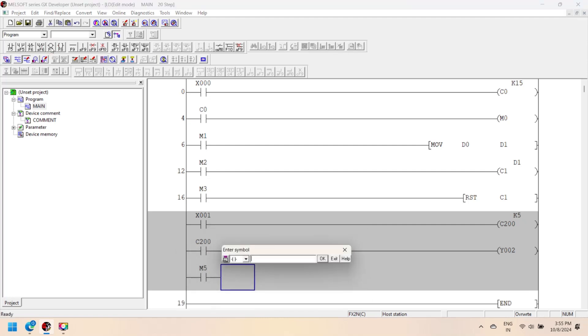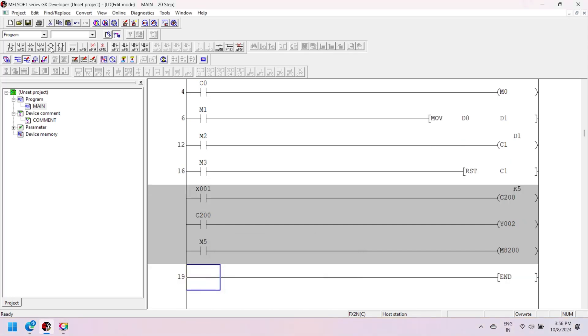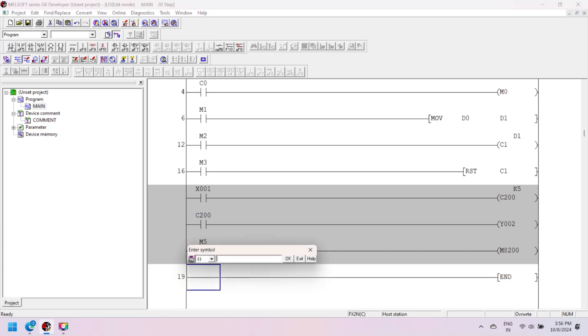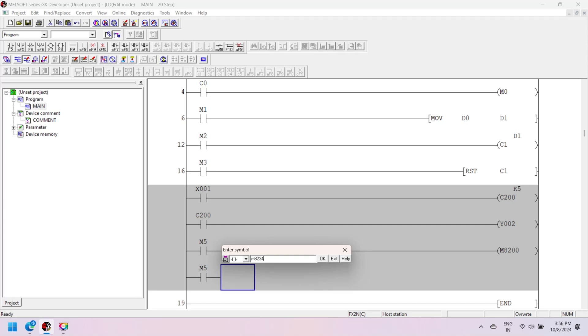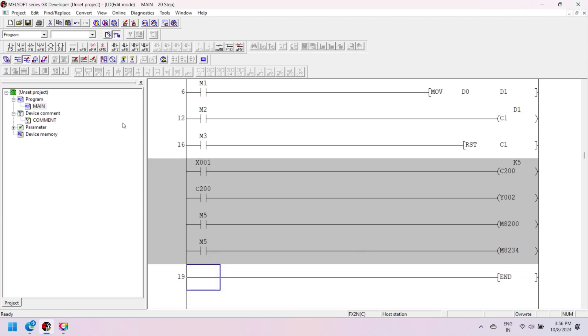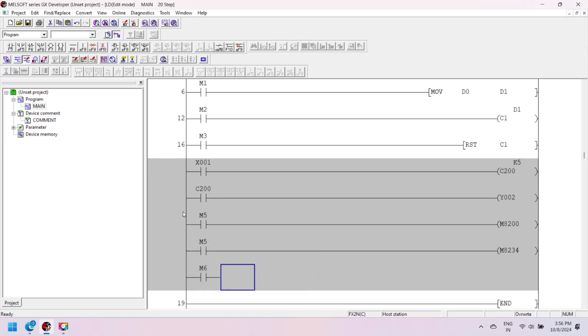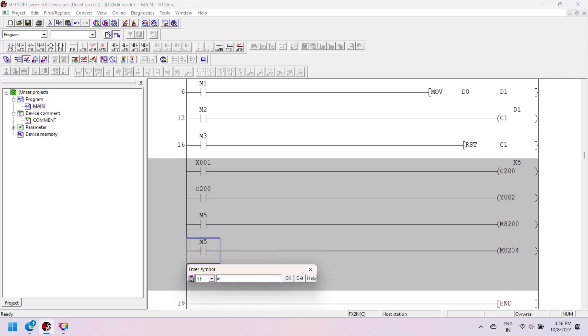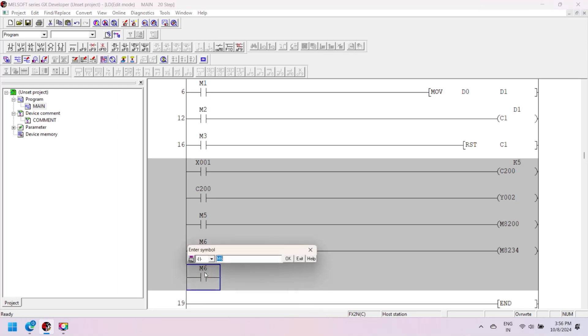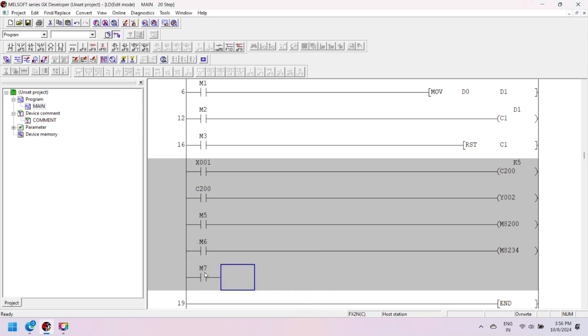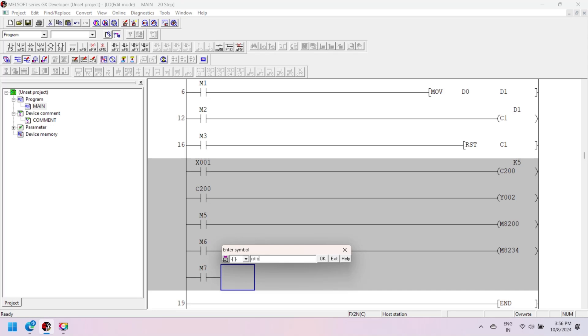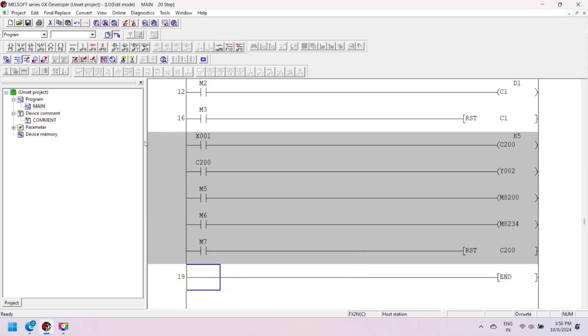M8200 is a special relay — when it is turned on, the counter works as a decrement or down counter. M8234 is also a special relay — if M8234 is turned on, the counter works as a general up counter or incremental counter. The device range for the Mitsubishi PLC general 32-bit bi-directional counter is C200 to C219, giving 20 devices available. You can use the RESET instruction to reset the bi-directional counter current value to zero. Now convert the program and re-download to the controller.